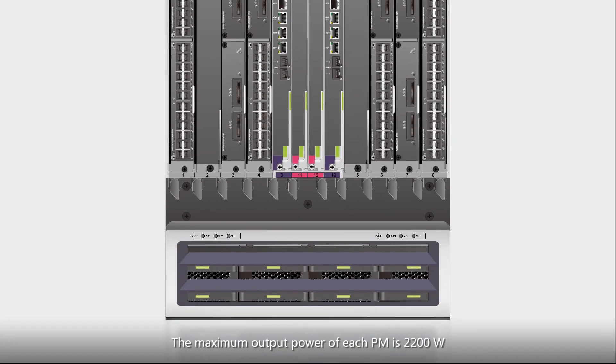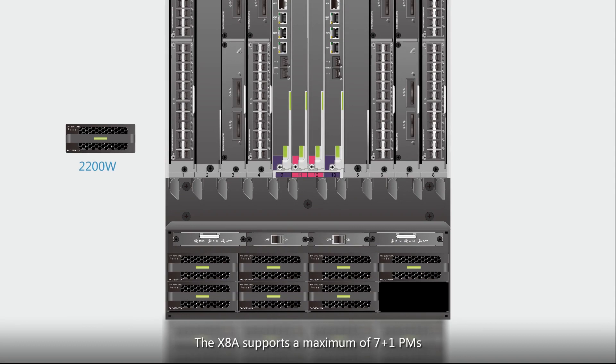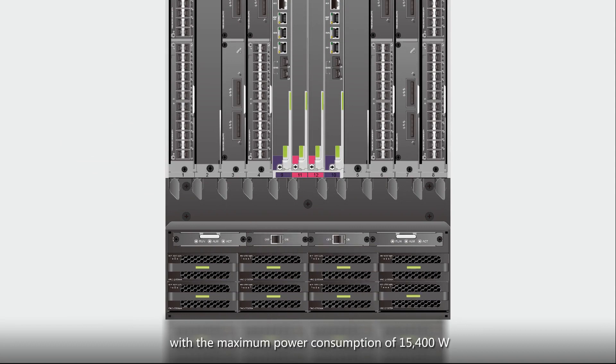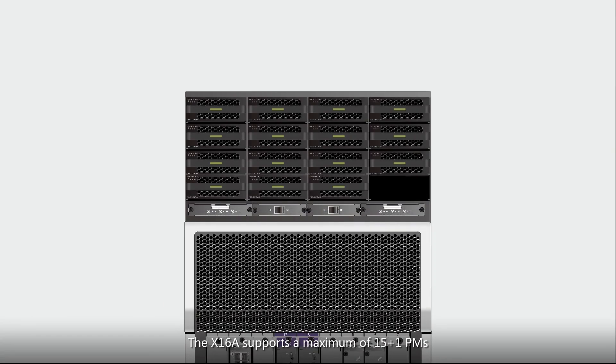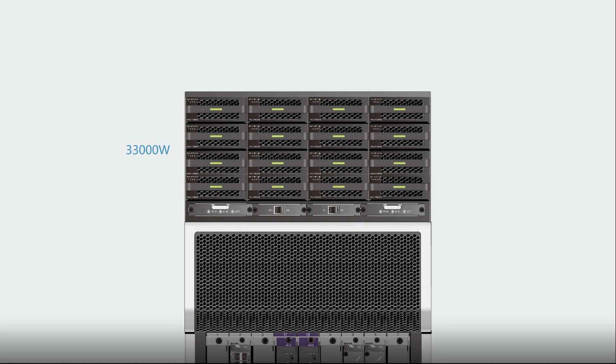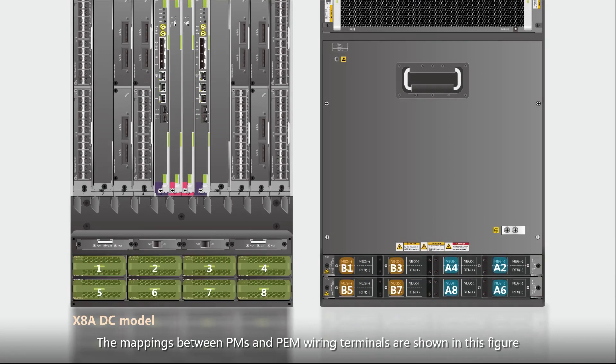The maximum output power of each PM is 2200W. The X8A supports a maximum of 7 plus 1 PMs with a maximum power consumption of 15400W. The X16A supports a maximum of 15 plus 1 PMs with a maximum power consumption of 33000W. The mappings between PMs and PEM wiring terminals are shown in this figure.